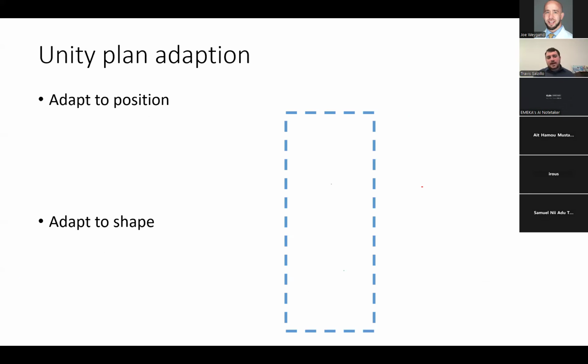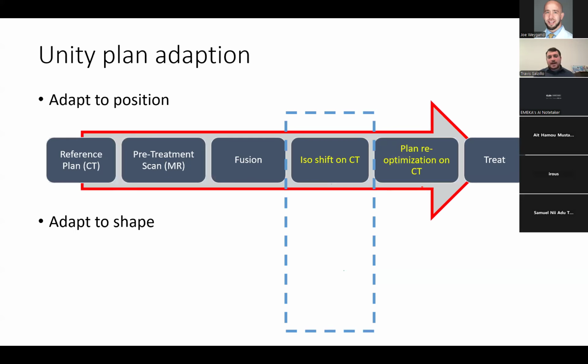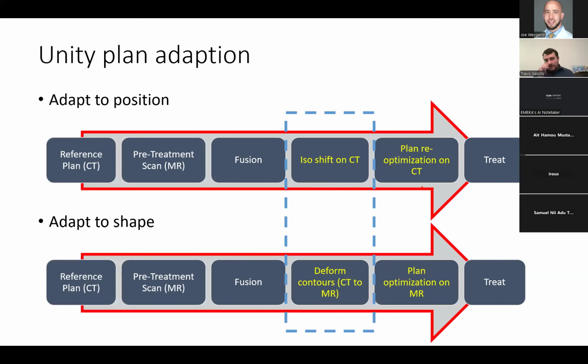There are two types of plan adaptation on the Unity. There's adapt to position and there's adapt to shape. These are the low level and high level plan adaptation I mentioned earlier. With adapt to position, essentially what it boils down to is that everything looks the same. It's just that your isocenter or your treatment target is offset by a few centimeters in any direction. And so you fuse your images, you calculate how much it's offset by, and you basically shift your MLCs and do a small amount of plan reoptimization to do a pseudo shift of the plan.